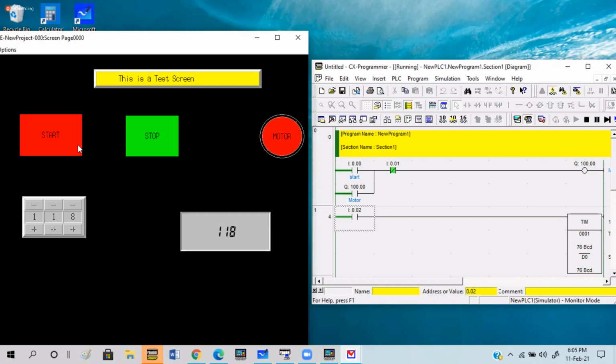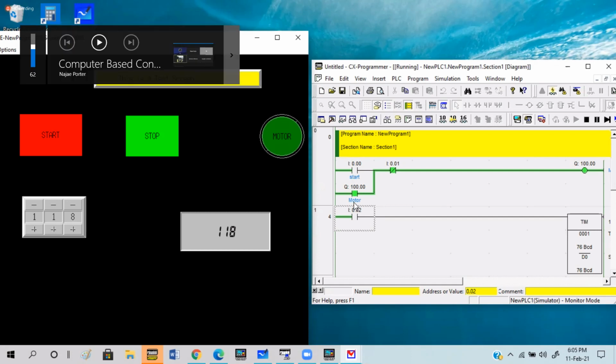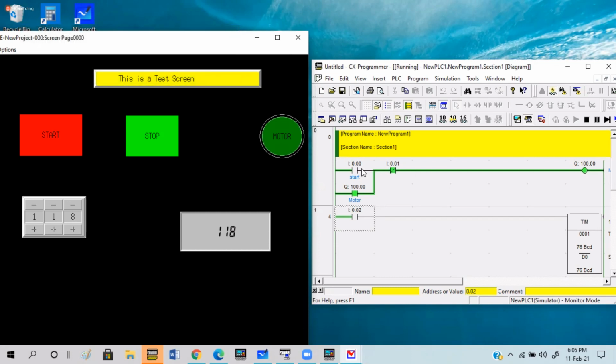We just indicate again. You press start, and as long as I have my hand down on the switch, it is on. But if I take my hand off the switch, it goes off. But I would want the motor to stay on. So this configuration, where I have the motor as the on switch, because these two are on switches, and the 0-1 is an off switch, is called a latch. Understood. All right.